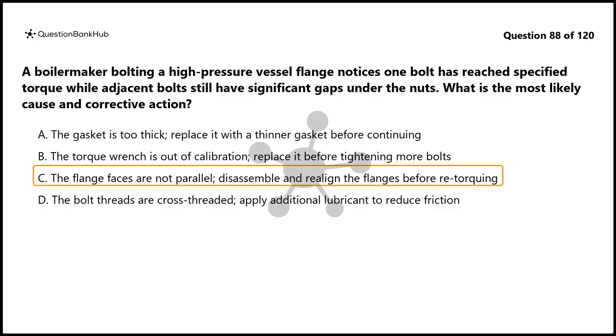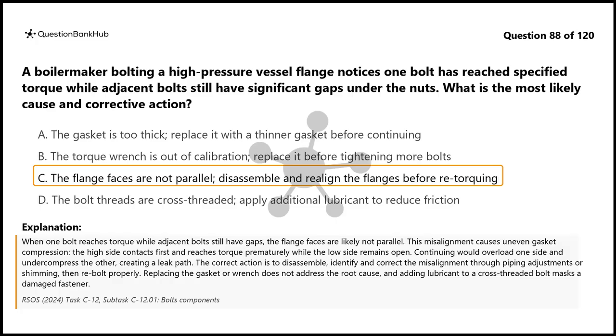The correct answer is C. When one bolt reaches torque while adjacent bolts still have gaps, the flange faces are likely not parallel. This misalignment causes uneven gasket compression. The high side contacts first and reaches torque prematurely while the low side remains open. Continuing would overload one side and undercompress the other, creating a leak path. The correct action is to disassemble, identify and correct the misalignment through piping adjustments or shimming, then rebolt properly. Replacing the gasket or wrench does not address the root cause, and adding lubricant to a cross-threaded bolt masks a damaged fastener.